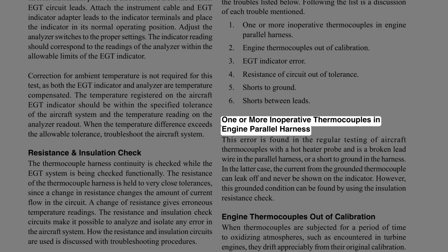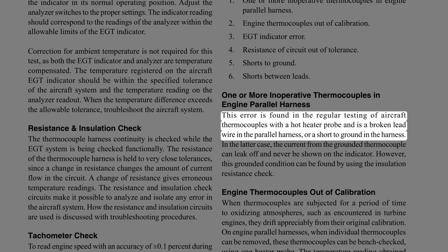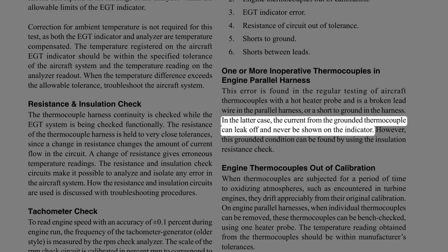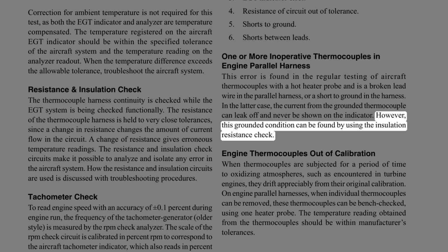One or more inoperative thermocouples in engine parallel harness. This error is found in the regular testing of aircraft thermocouples with a hot heater probe and is a broken lead wire in the parallel harness, or a short to ground in the harness. In the latter case, the current from the grounded thermocouple can leak off and never be shown on the indicator. However, this grounded condition can be found by using the insulation resistance check.